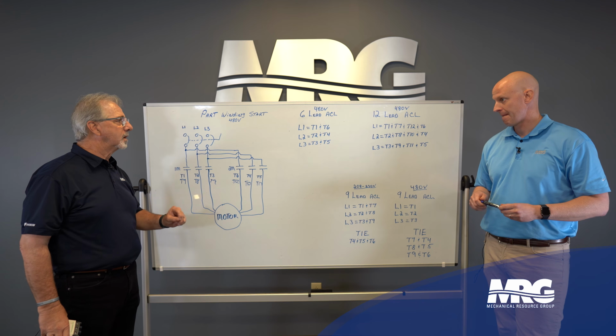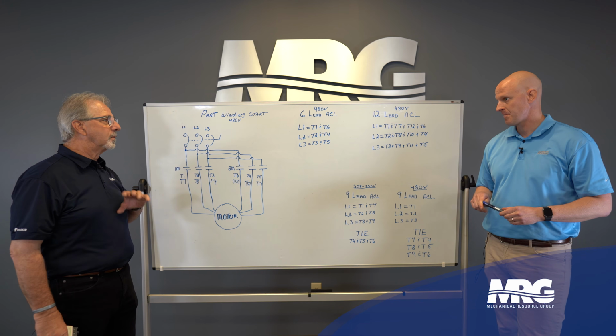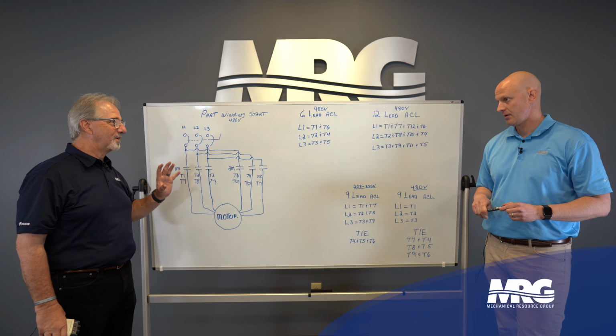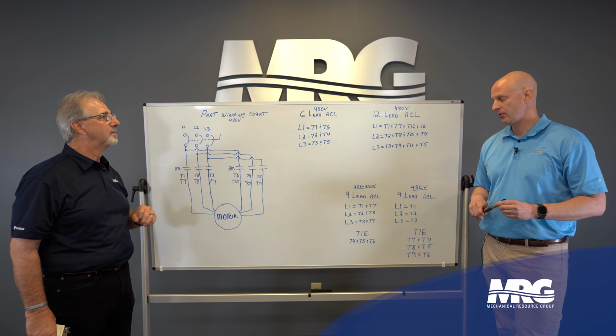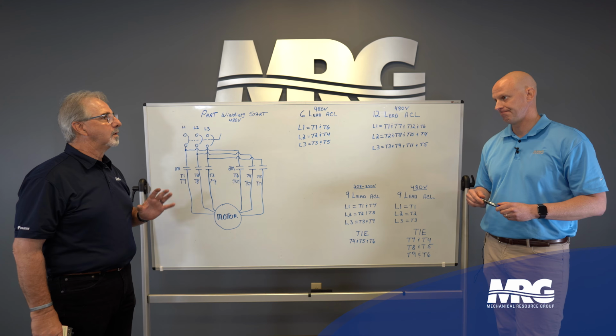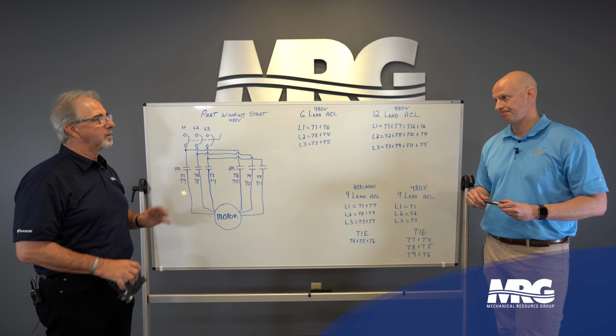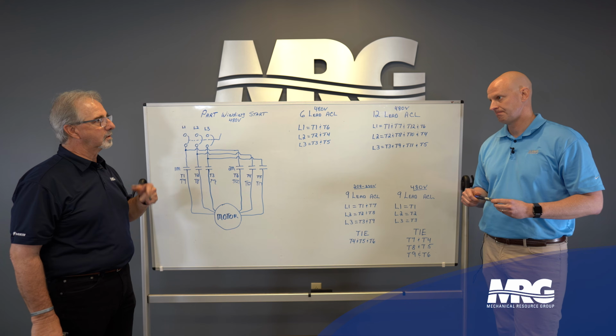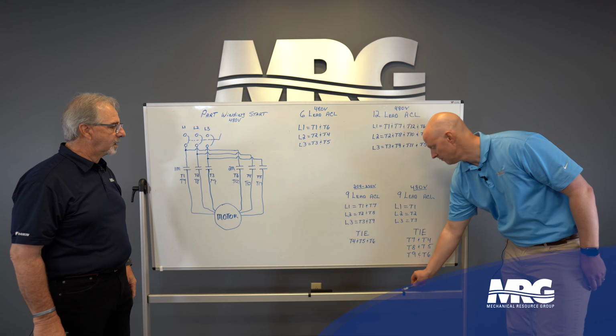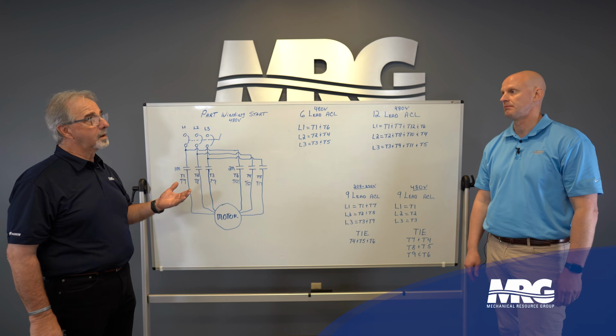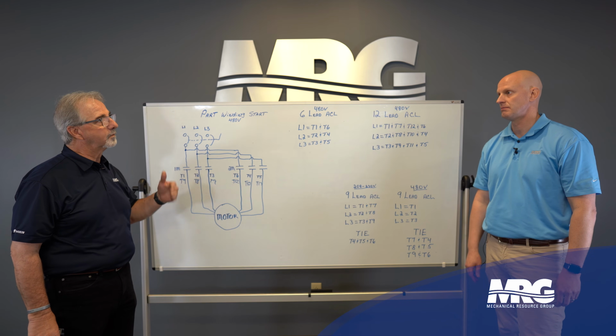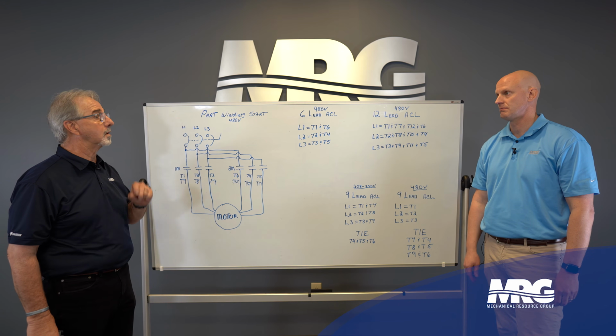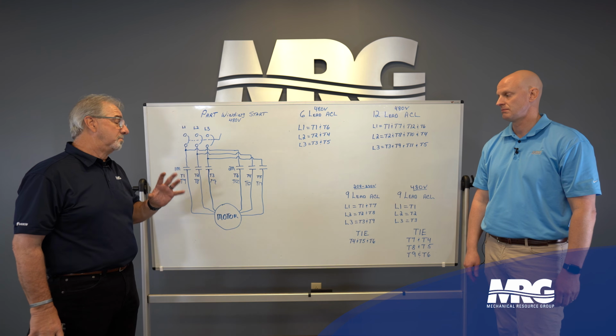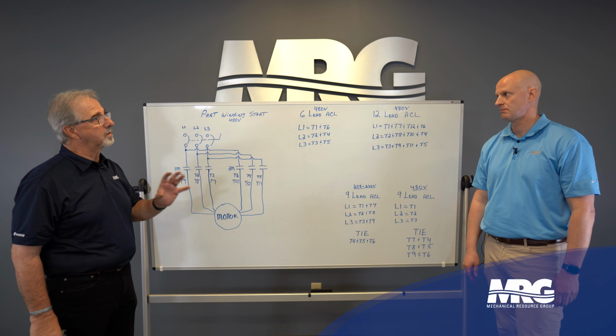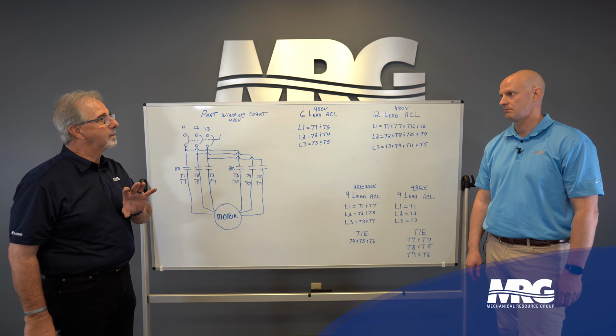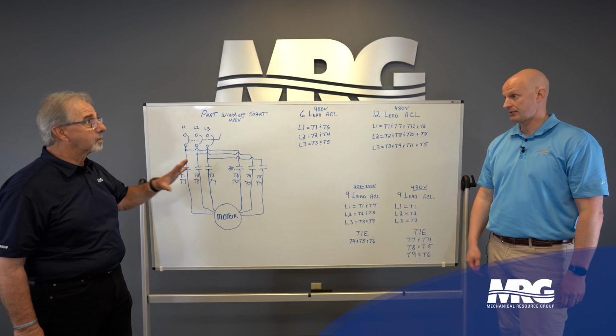That'd be great. But really, motors are, like I said, a dumb animal doing a very specific role. Well, you order the wrong motor, you can make your job really hard. You order a 9-lead motor and it's a part winding start or a Wye-Delta, good luck with that. Yeah. There are some 9-lead motors you can, but you need to refer to manufacturer specification on how to connect that, because it's not going to be consistent manufacturer to manufacturer. Okay? Okay. So that kind of covers part winding start and across the line.